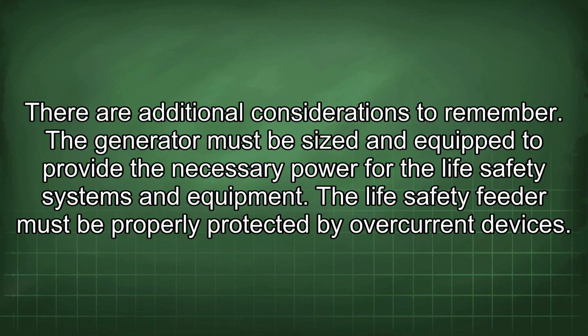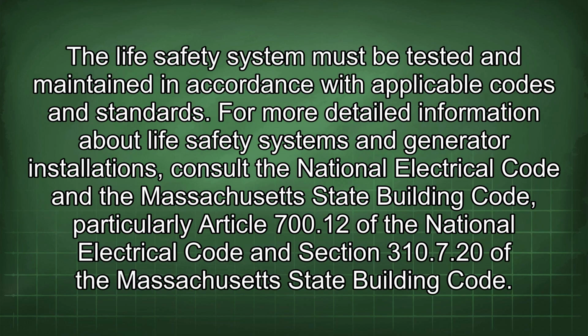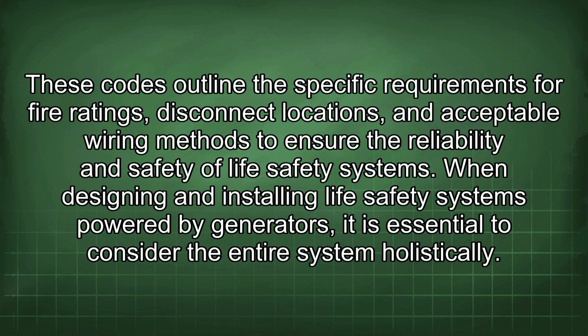There are additional considerations to remember. The generator must be sized and equipped to provide the necessary power for the life safety systems and equipment. The life safety feeder must be properly protected by overcurrent devices. The life safety system must be tested and maintained in accordance with applicable codes and standards. For more detailed information about life safety systems and generator installations, consult the National Electrical Code and the Massachusetts State Building Code, particularly Article 700.12 of the National Electrical Code and Section 310.7.20 of the Massachusetts State Building Code. These codes outline the specific requirements for fire ratings, disconnect locations, and acceptable wiring methods to ensure the reliability and safety of life safety systems.